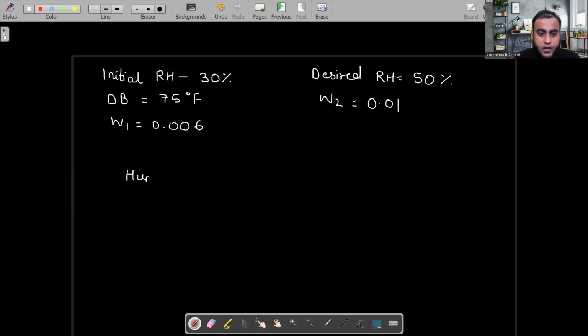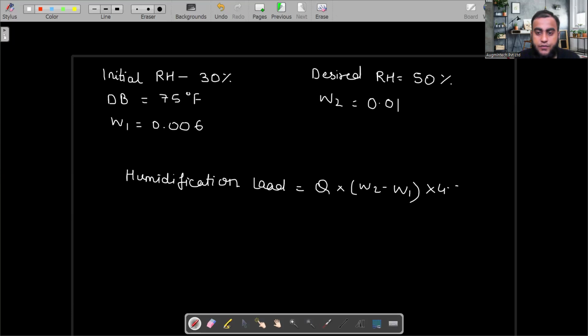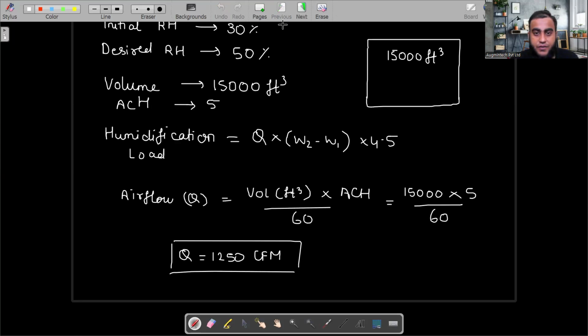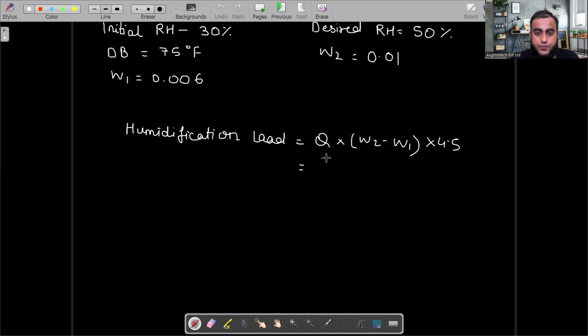So the humidifier, to calculate the humidification load, tell me the formula, all of you. Let me know, please, in the chat box. What is the formula? We have to use Q, the airflow rate, times W2 minus W1, times 4.5. So airflow rate, how much have we calculated? You can see the previous page for that. 1250 CFM. Okay, so write down here 1250 CFM, and W2 value 0.01 minus W1 0.006, into 4.5.